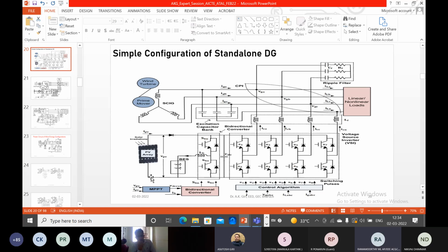Similarly here, suppose you want to generate 3 kilowatt, 4 kilowatt, 5 kilowatt, accordingly you have to select the number of strings, and then you have to see what the string voltages are, the open circuit voltage VOC and the short circuit current, and then by using the MPPT algorithm, you have to see at which potential level you are coming, whether it is matching with the DC level or not. So accordingly, you can change the design of the PV. There is no specific method for how to select. It will be some trial and error, and it will be based on your experience how to put the parameters for the source part, right?